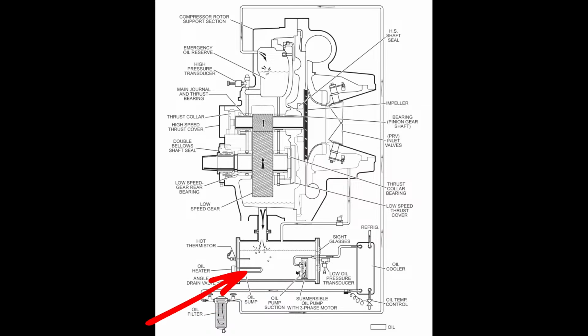Another one I'd want to check is, is the oil heater actually turning off? The older systems have a thermostat on the back of the oil heater. It's supposed to be set for 180 degrees. And then the control panel also controls a relay on the I/O module underneath the microboard that triggers this. So there's actually two layers of temperature control you're supposed to have. One is the I/O module engaging the oil heater through that relay, which I think is the K1 relay if I'm not mistaken. I'm pulling off a memory there, so I'd have to look that up to verify it. But off of the I/O module, you've got an oil heater relay.